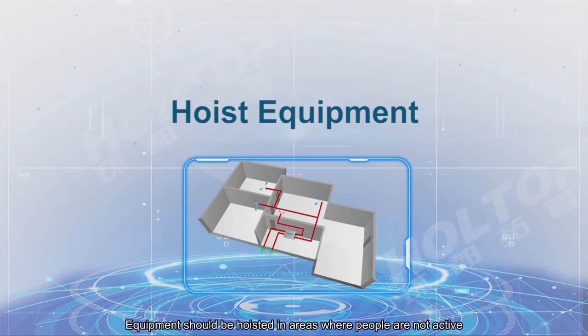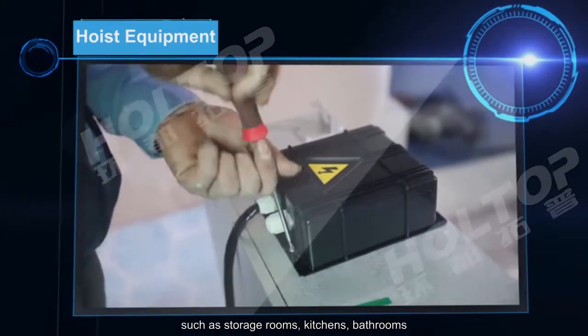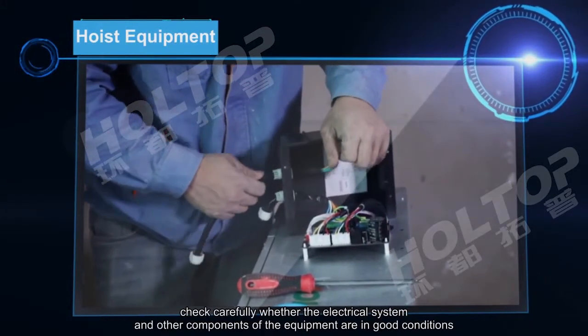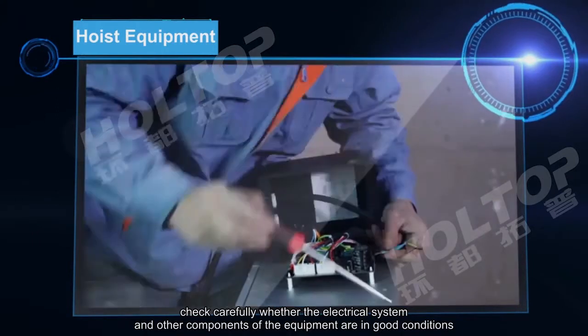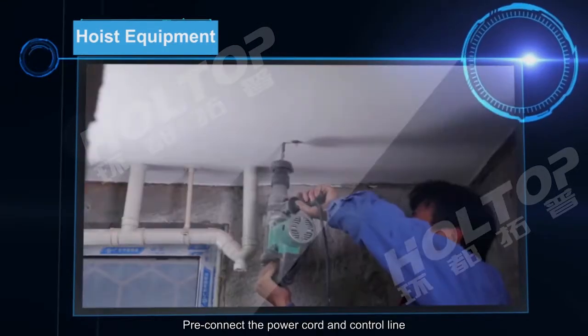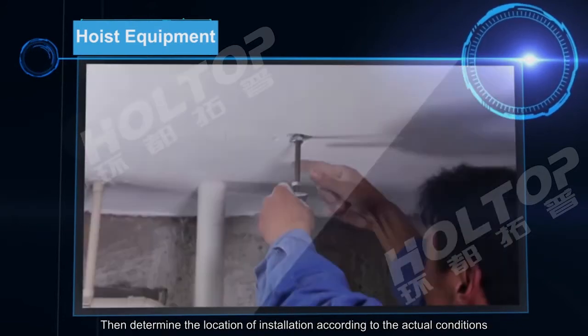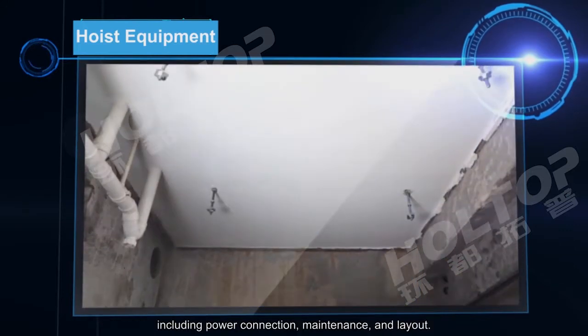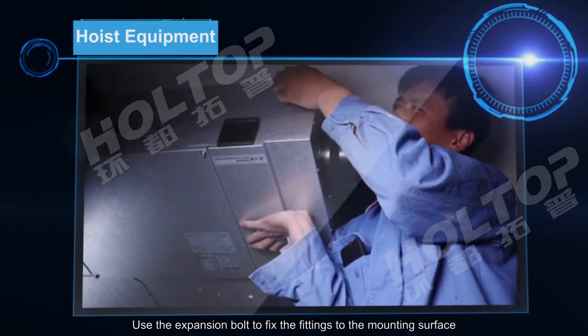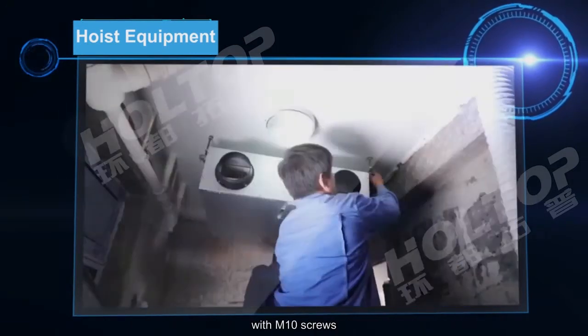Equipment should be hoisted in areas where people are not active, such as storage rooms, kitchens, and bathrooms. Before installing the equipment, check carefully whether the electrical system and other components are in good condition. Pre-connect the power cord and control line, then determine the location of installation according to actual conditions, including power connection, maintenance, and layout. Use the expansion board to fix the fittings to the mounting surface with M10 screws.